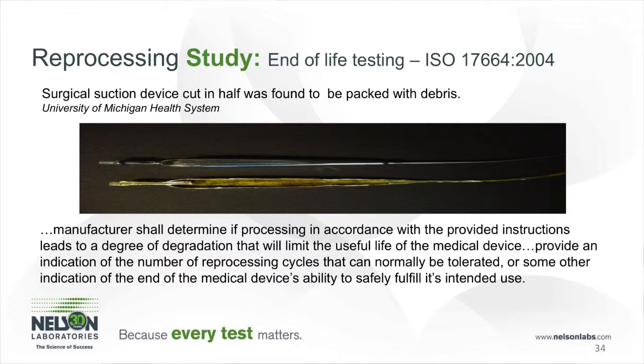One more thing that I wanted to talk about was end of life testing. FDA is now requiring manufacturers to determine what that looks like. Since the healthcare facility does not always count the number of cycles every single medical device goes through, medical device manufacturers need to have specific instructions that state when a medical device is at its end of use life. So, different ways to tell when the device cannot be utilized further.